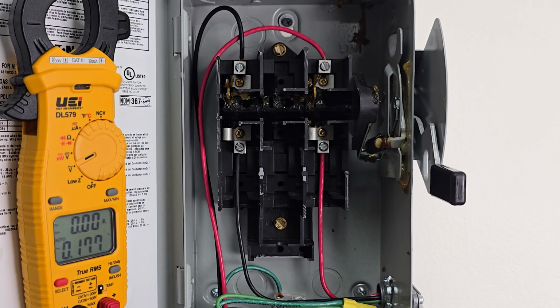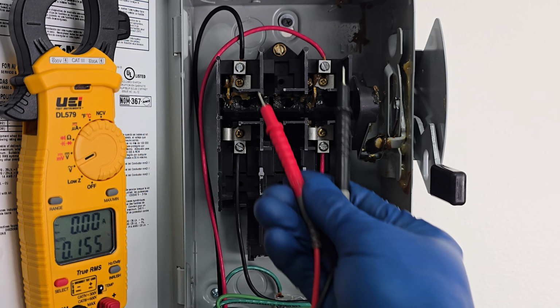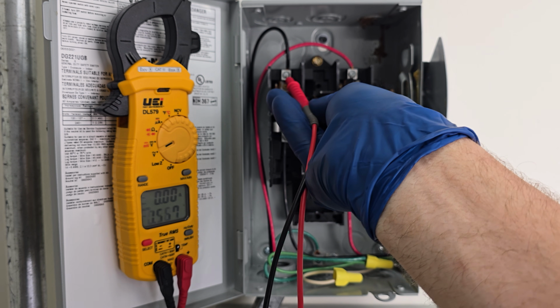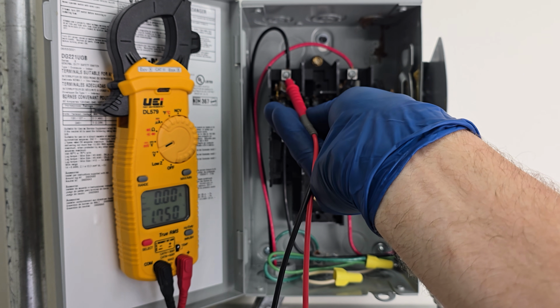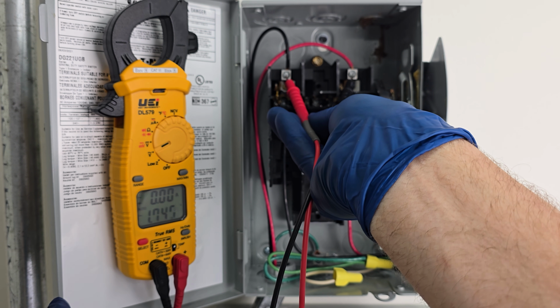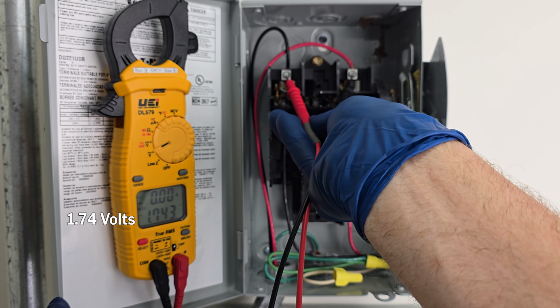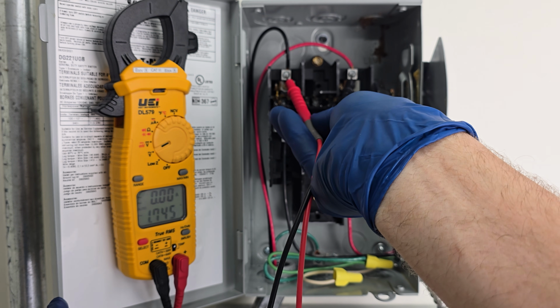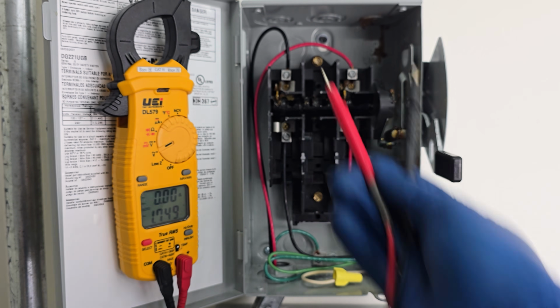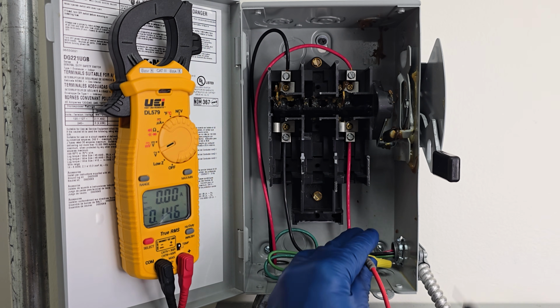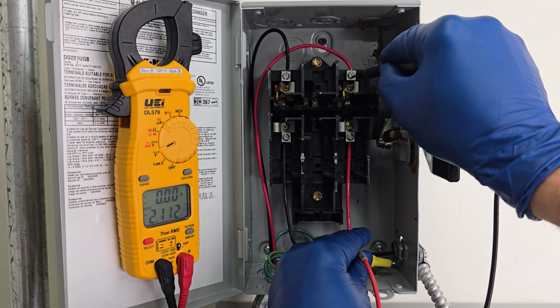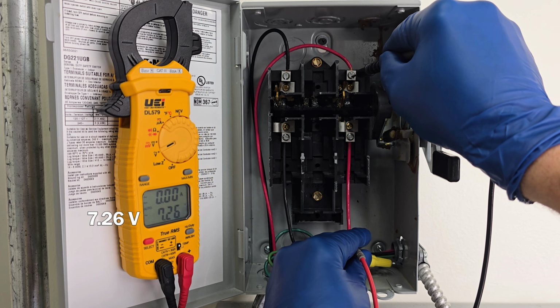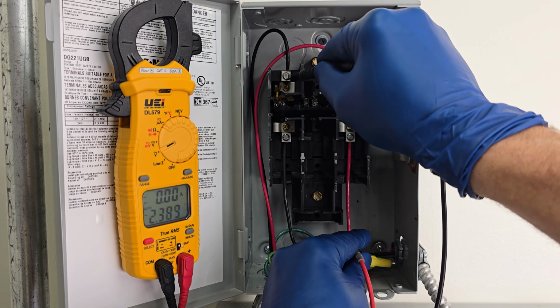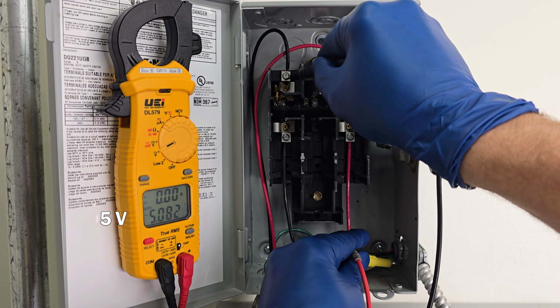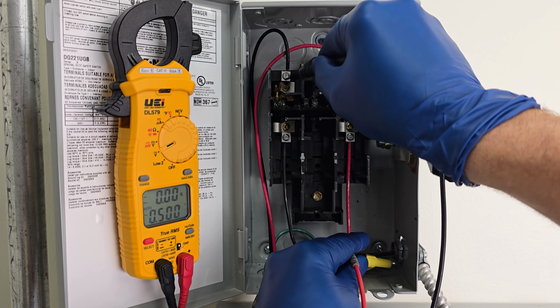So if we were to perform work in this disconnect box, we'd want to turn the power off at the main breaker, which is what I just did, and now we're measuring the voltage. You see we're measuring 1.74 volts, and that means that the power is actually off. And so let's measure between ground and this terminal. You see we're measuring 7.26 volts. And then over here we're measuring 0.5 volts. But that actually means that the power is off.